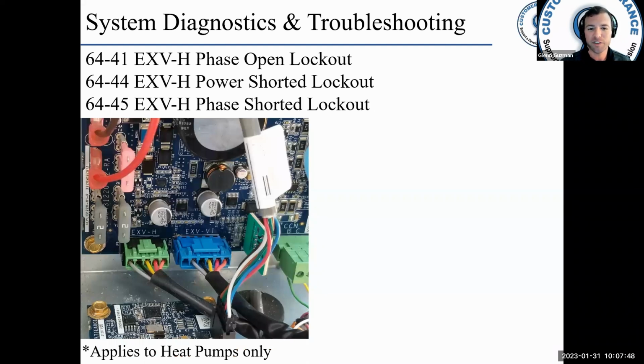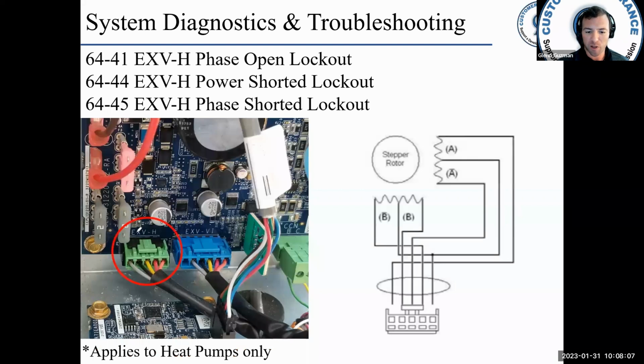6441 EXV for heating. This is a phase open lockout. 6444 and 6445, that's the power shorted lockout and phase shorted lockout. This applies to the heat pumps only because you have an EXV in heating for heat pumps. Okay. You can see the plug here on the left. Okay, 5 pins. This diagram is out of the manual. You got a couple different phases there.